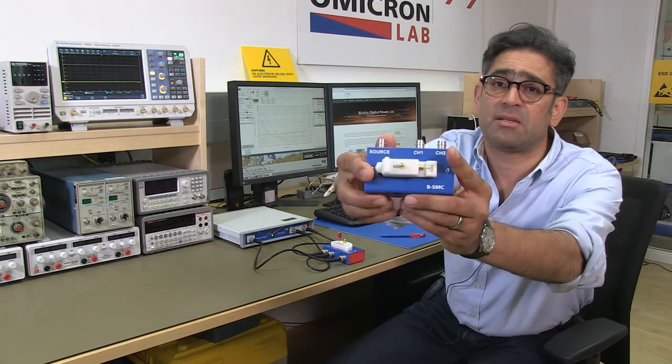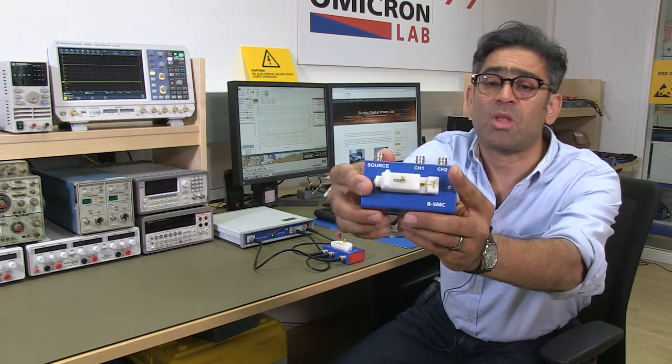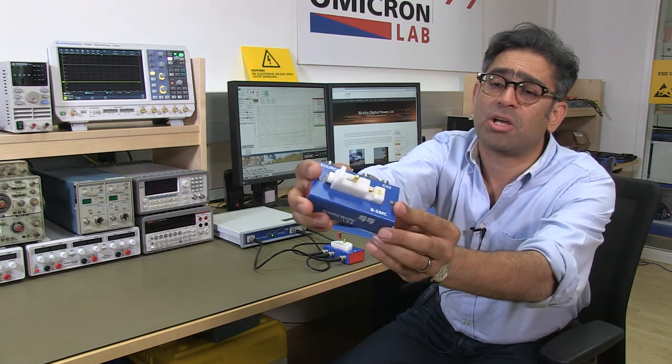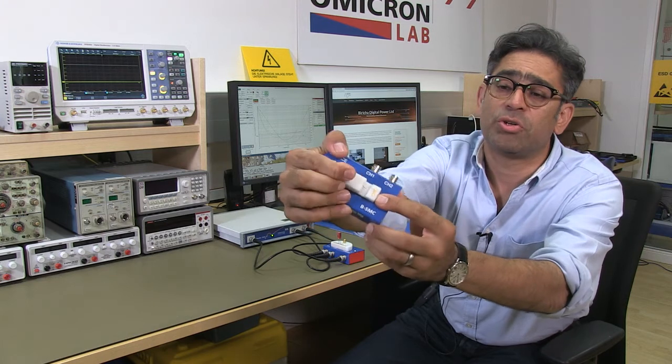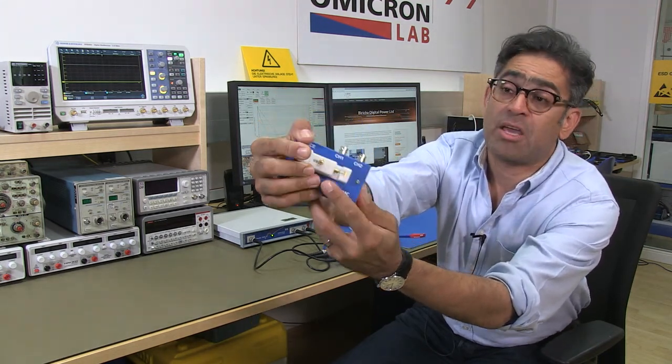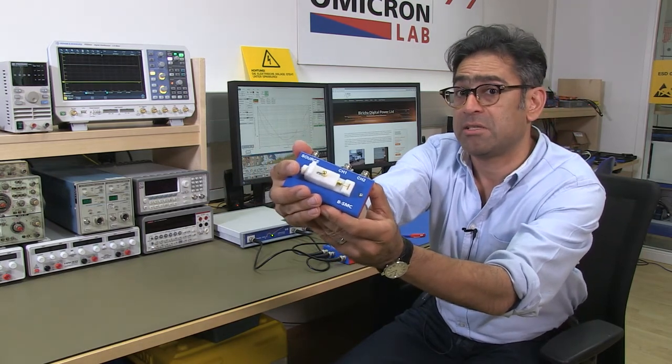This becomes particularly important when you deal with surface mount components. And that's why there is a second impedance adapter which Omicron has designed so that you could actually put your surface mount component in here and then make a correct measurement without the impact of the component leads.